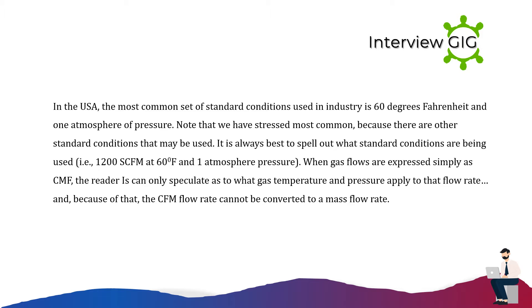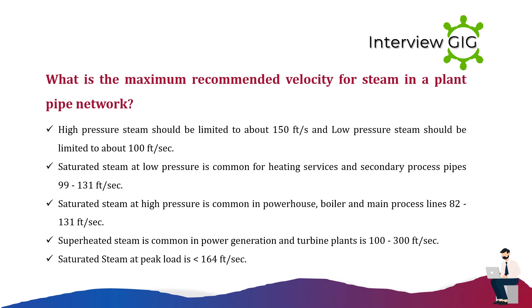What is the maximum recommended velocity for steam in a plant pipe network? High-pressure steam should be limited to about 150 feet per second and low-pressure steam to about 100 feet per second. Saturated steam at low pressure, common for heating services and secondary process pipes, is 99 to 131 feet per second. Saturated steam at high pressure, common in powerhouse boilers and main process lines, is 82 to 131 feet per second. Superheated steam, common in power generation and turbine plants, is 100 to 300 feet per second. Saturated steam at peak load is less than 164 feet per second.